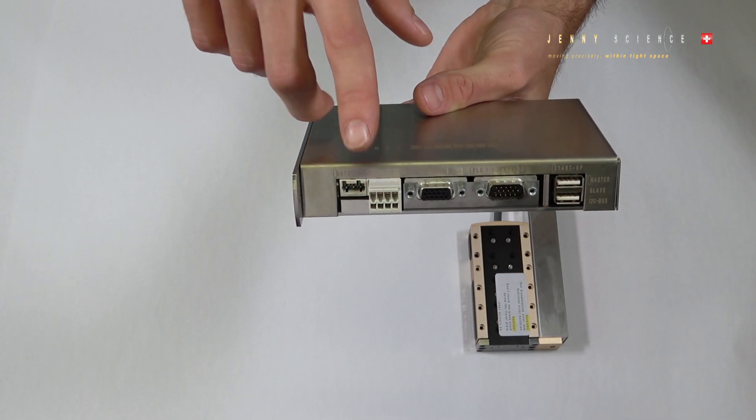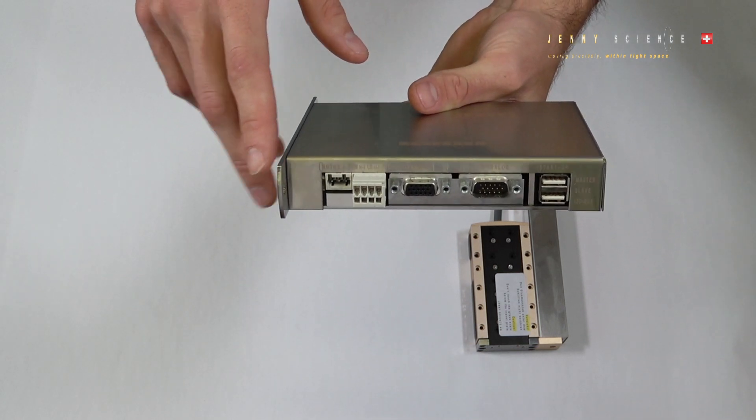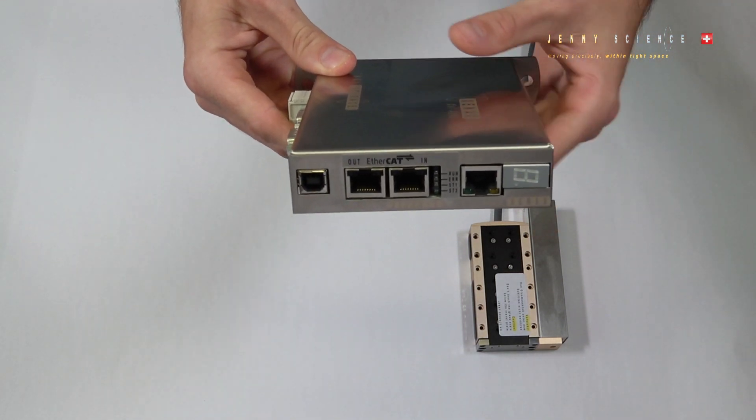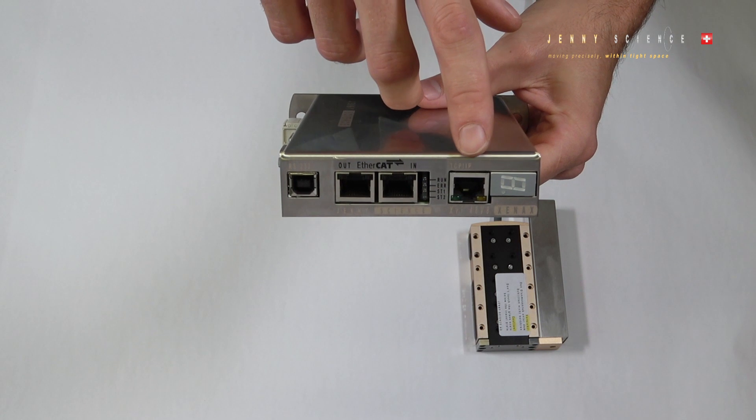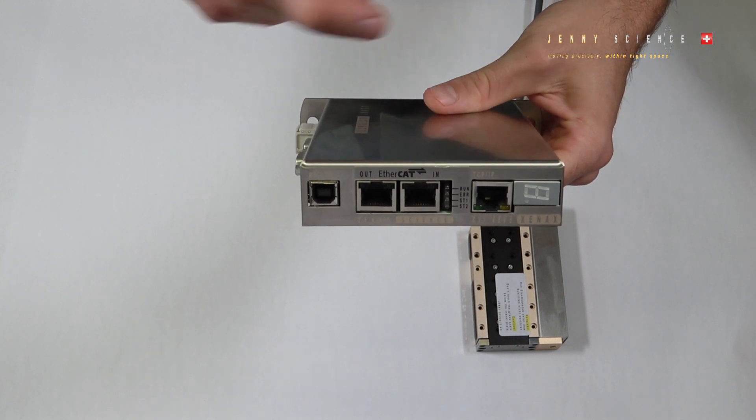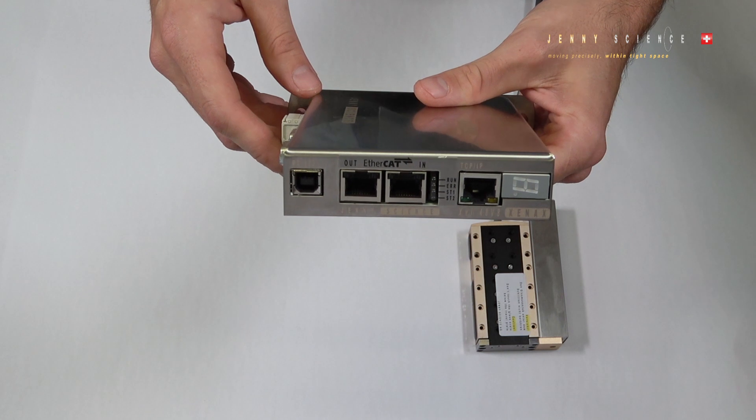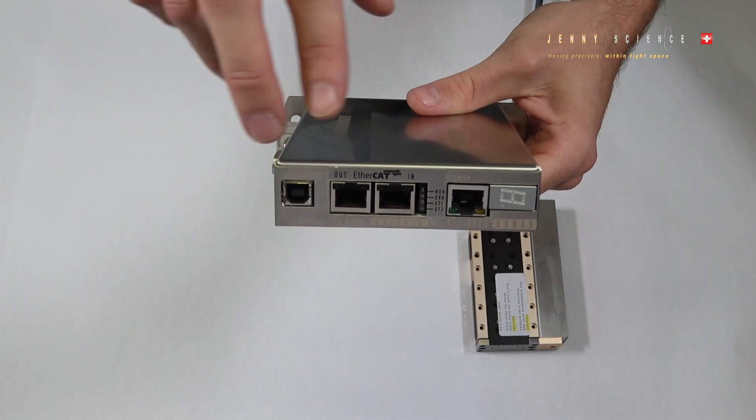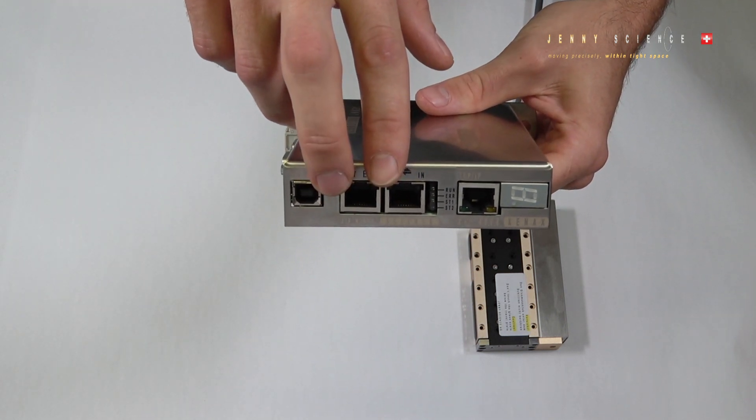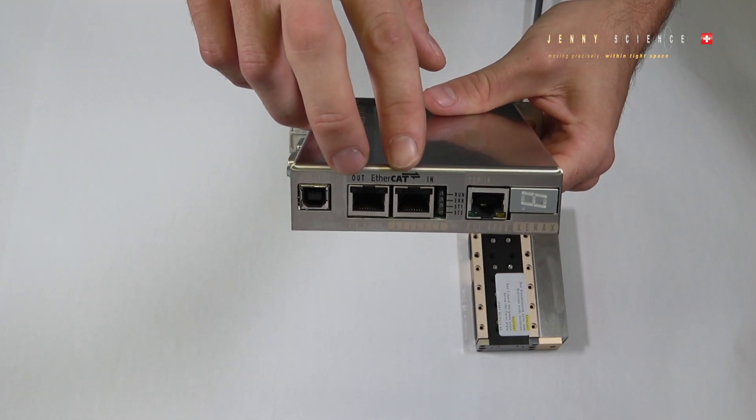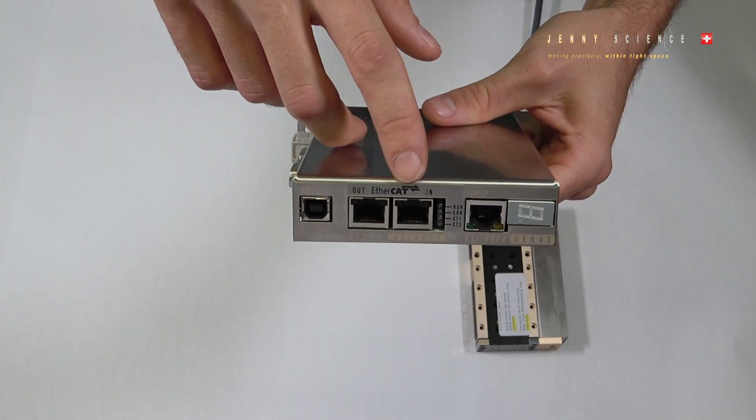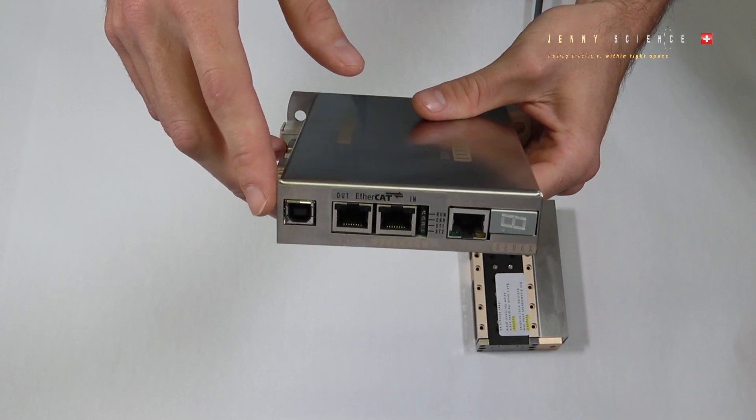Very important here are the two interfaces. We have a standard TCP IP interface with a web server integrated so you can connect to it very easily by using a web browser. Additionally here we have a field bus module to connect the controller to any PLC environment you like. For example EtherCAT, Ethernet IP, Powerlink or Profinet.